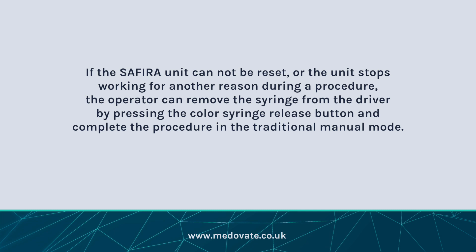If the SAFIRA unit cannot be reset, or the unit stops working for another reason during a procedure, the operator can remove the syringe from the driver by pressing the coloured syringe release button and complete the procedure in the traditional manual mode.